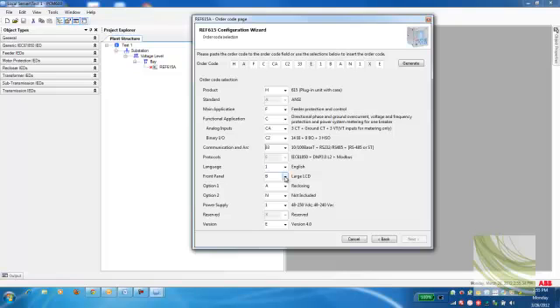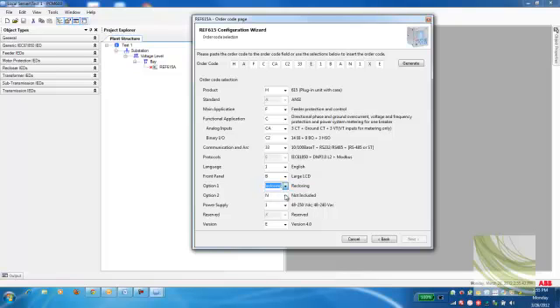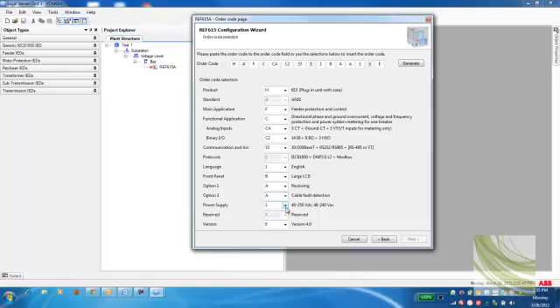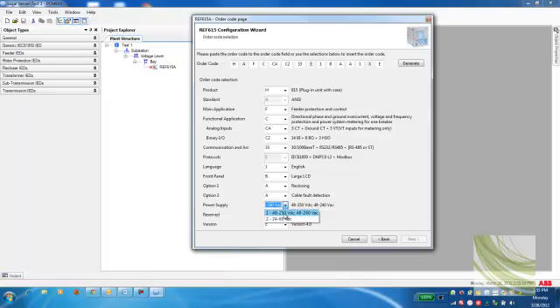English is fine. We'll have a large LCD display. Option 1, we're going to select that it does have reclosing. And option 2, we'll say that it has cable fault detection built into the style number. Here, we also need to select on power supply whether it's 24 to 60 volt DC or it's a combination 48 to 250 volt DC, 48 to 240 AC. That's the selection we'll choose at this point in time.